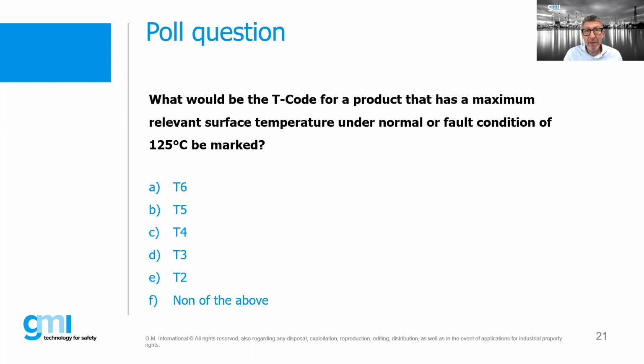A barrier, for example, a GMI barrier, is certified for zone 2 installation also, and therefore has a marking. The marking indicates how hot they can get under test, under full fault condition. And there's also some margin, if I remember correctly, you cannot reach. It says 160, you cannot go to 159.9, I don't remember the standards, but anyhow. So it's an easy answer because it's the most common code you find out there.